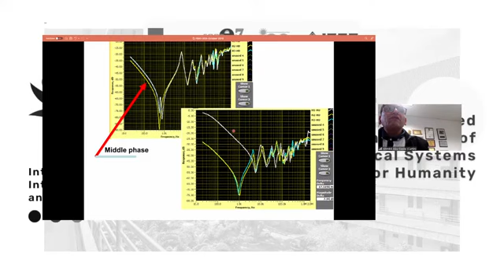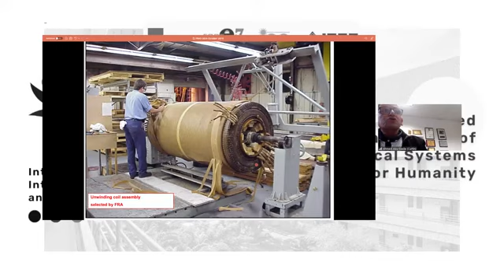But when you look at another signature, this one here, even if you don't have any experience with the frequency response analysis, you will observe that one of them is significantly deviated from the others in the low frequency range, which means that this transformer has something wrong in this phase. So what we have to do is to take the transformer out of service and unwrap the winding. The suspected winding was this one here. So we have to take it outside to the workshop and take the papers out, unwrap it.